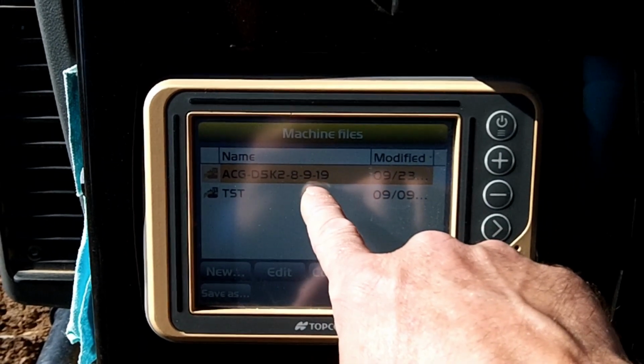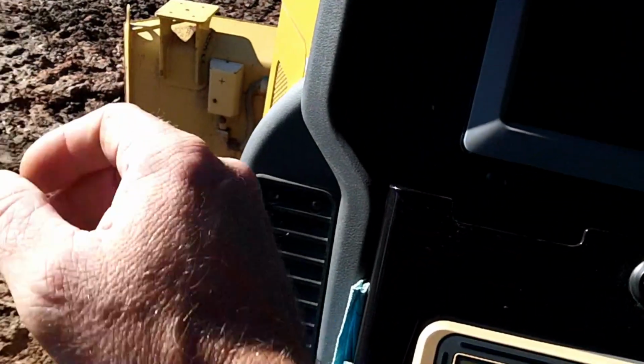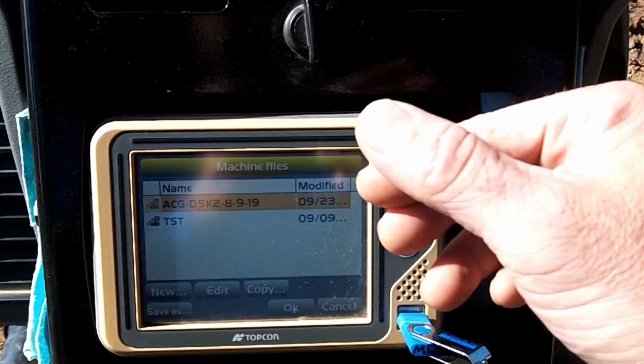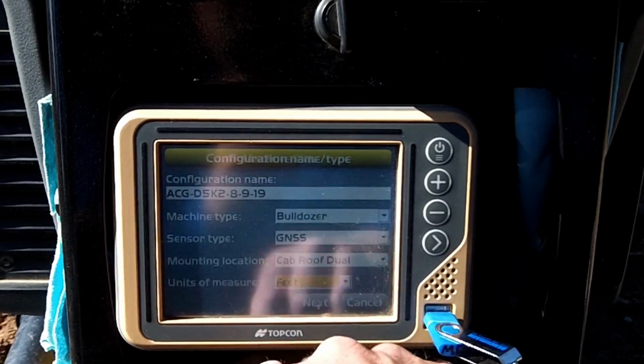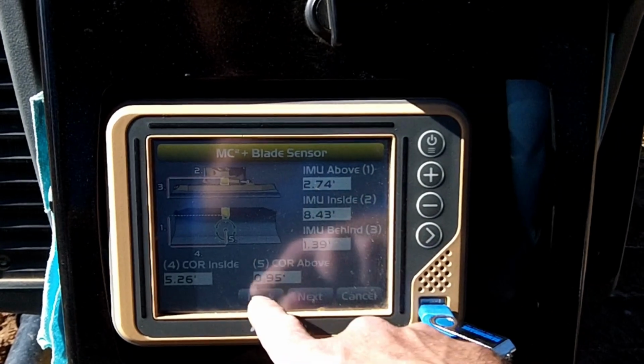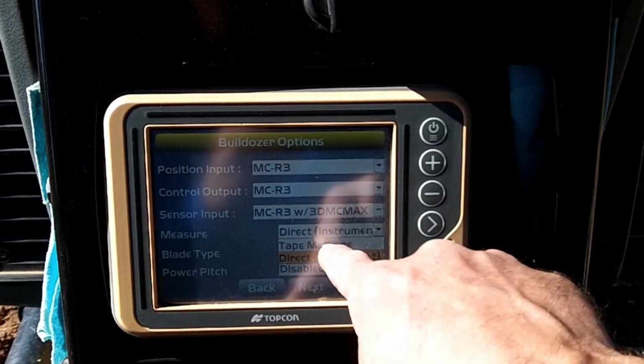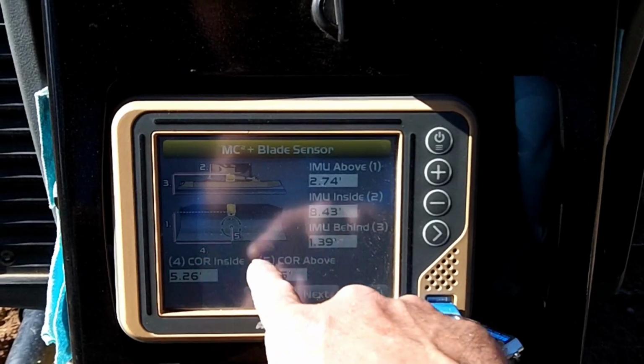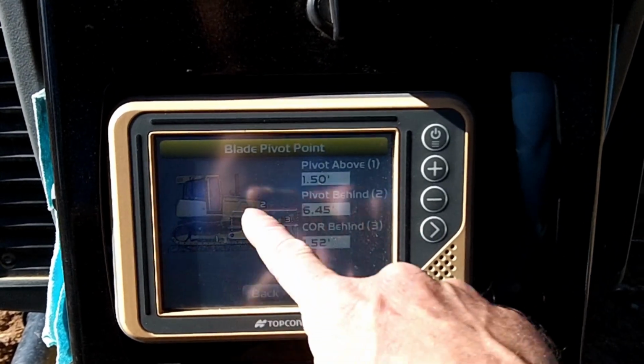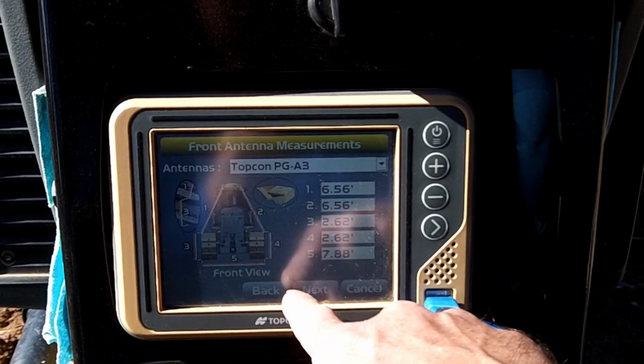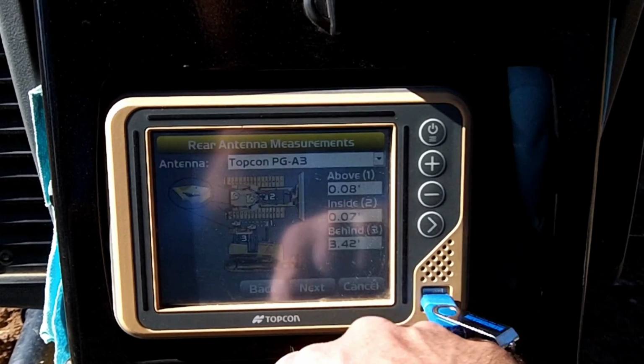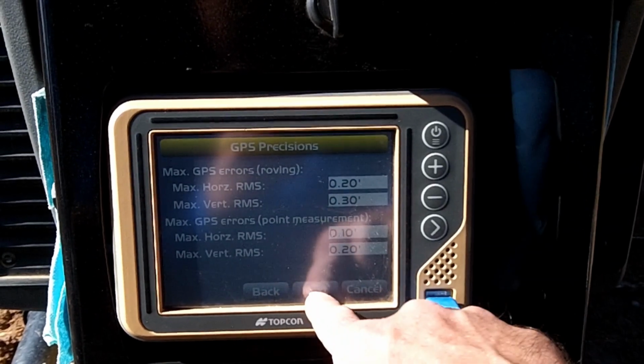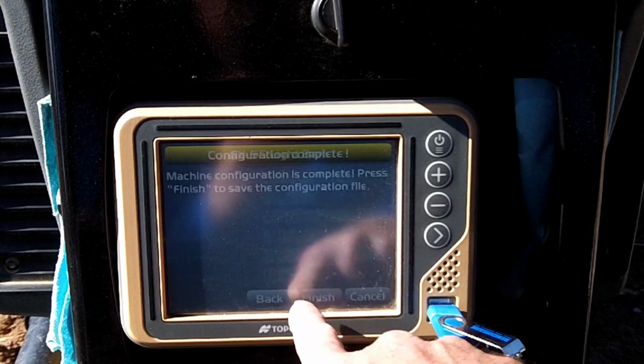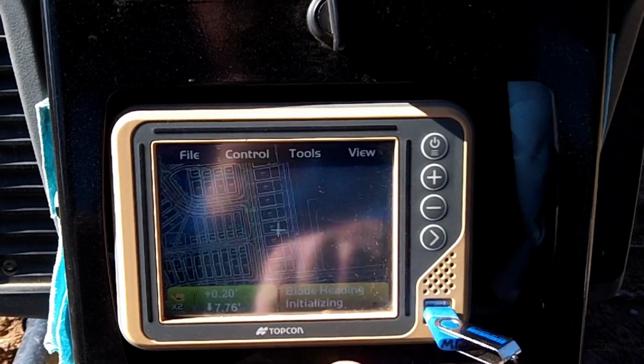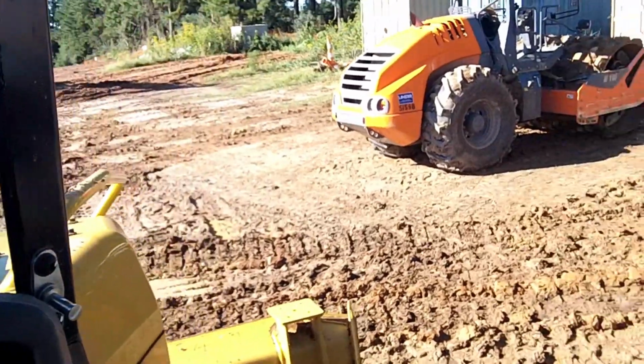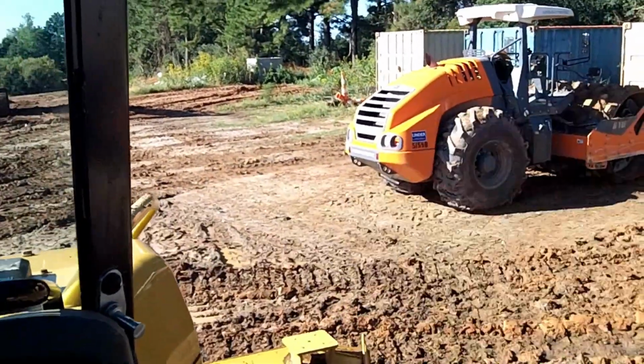And the last time it was done was 2019, so I'm sure there's a little bit of wear here and there, so we'll retake measurements and we'll actually recalibrate this machine, and check them against actually used a direct instrument. I'm going to use a tape measure, and we'll check all these numbers, measurements against what I take, and we'll get this machine tied right into the project nice and tight, and get them back to work. So let me move this machine someplace up on higher, drier ground.